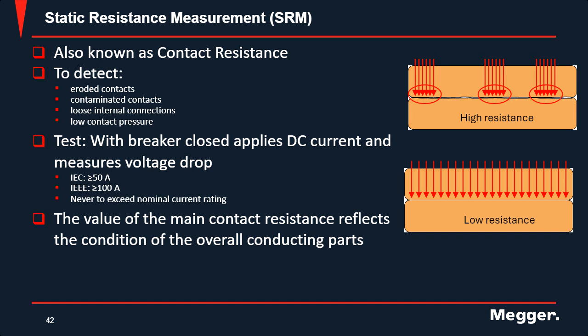So the value of the main contact resistance reflects the condition of the overall conducting parts. I would like to point out, if you do this on an SF6 breaker that has the main contact and an arcing contact, you are only going to get the resistance of the main, of the whole body itself. In order to figure out the resistance of your arcing contact, you have to do the DRM test, which we're about to talk about in a second.